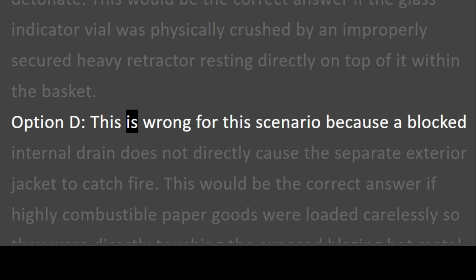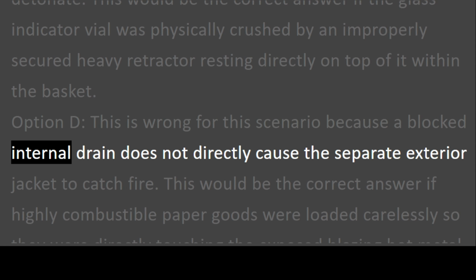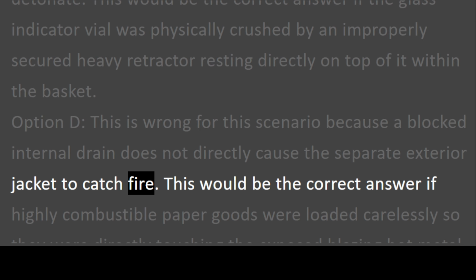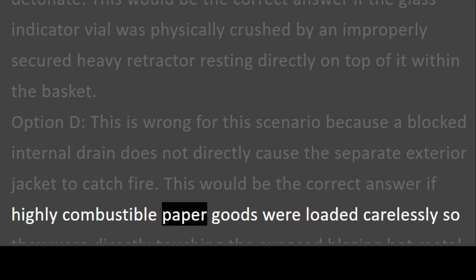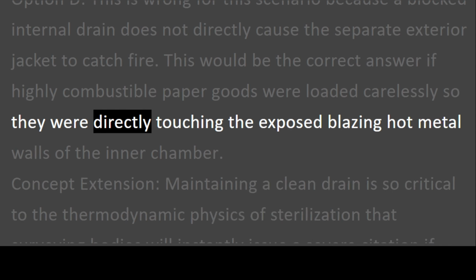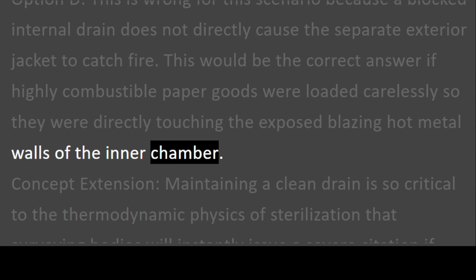Option D. This is wrong for this scenario because a blocked internal drain does not directly cause the separate exterior jacket to catch fire. This would be the correct answer if highly combustible paper goods were loaded carelessly so they were directly touching the exposed blazing hot metal walls of the inner chamber.